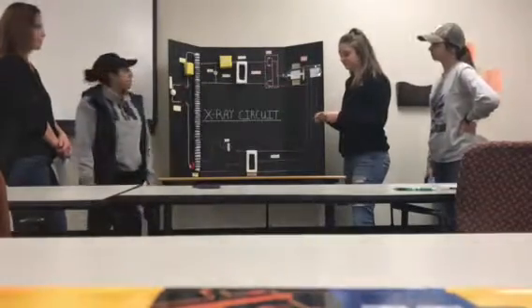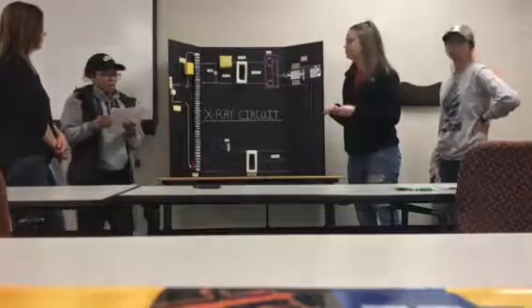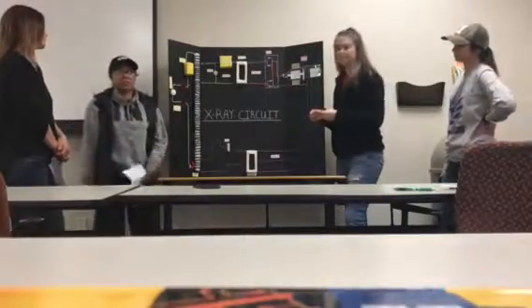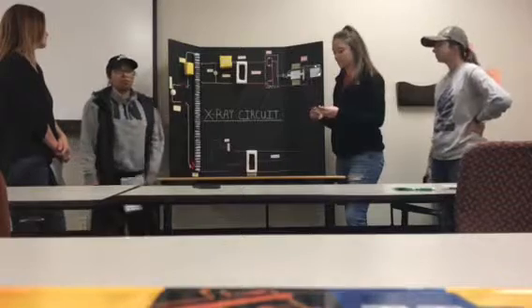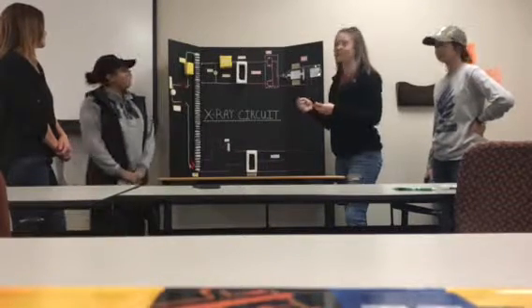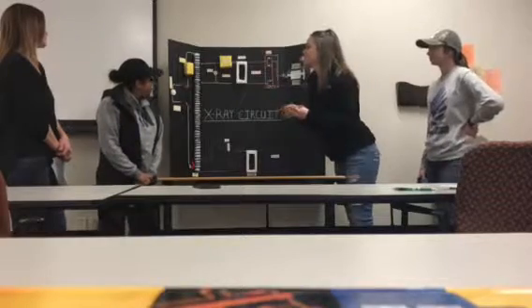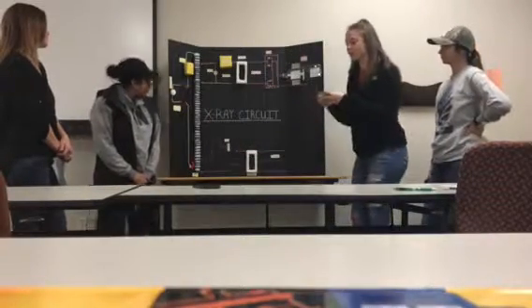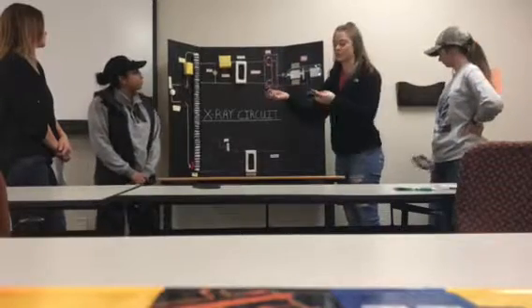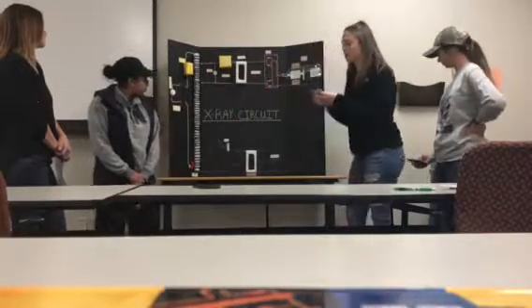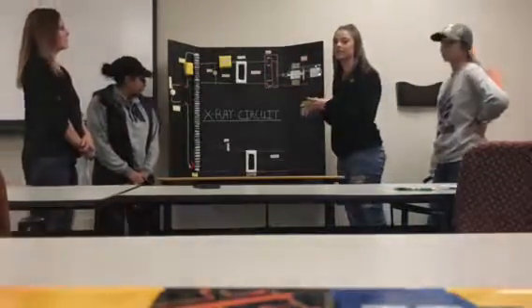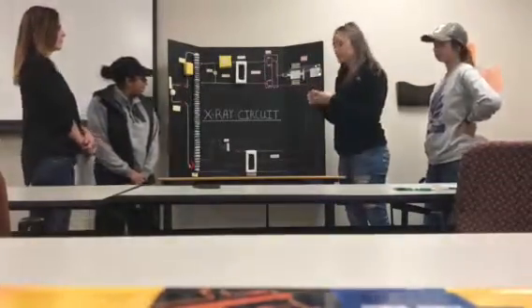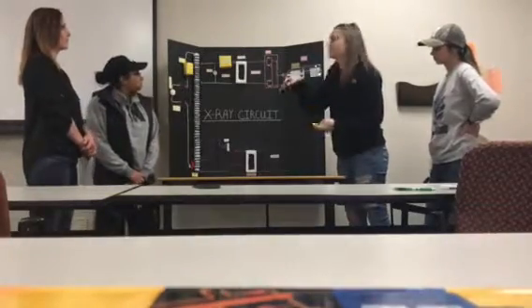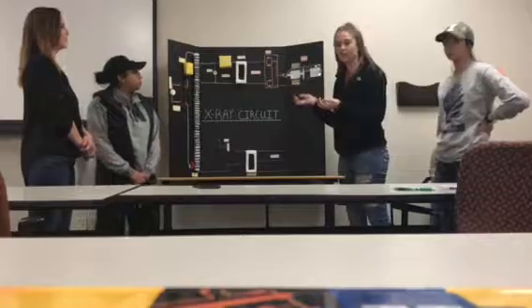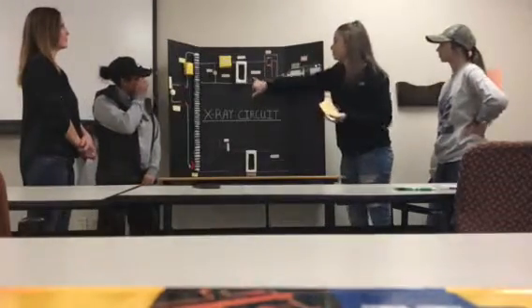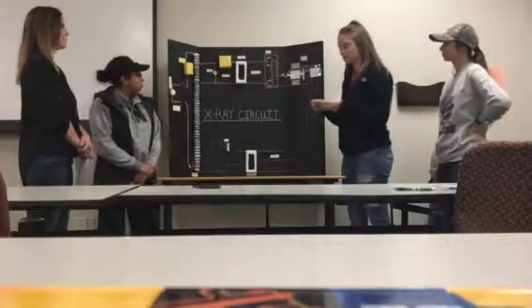Also part of the primary circuit is the circuit breaker, and this protects against short circuits and shock hazards, and it opens and breaks the flow of electricity. Alright, and then as for the auto transformer, which is what the line compensators are connected to, as I think she just mentioned, it is an adjustable transformer, and it's controlled by the KVP selector, which is on the operating console. And since you are selecting the KVP, it's self-induction, unlike these two, which you'll learn about later, which is mutual induction.